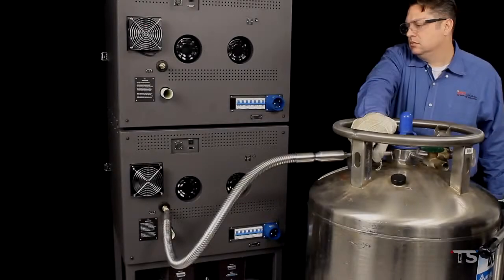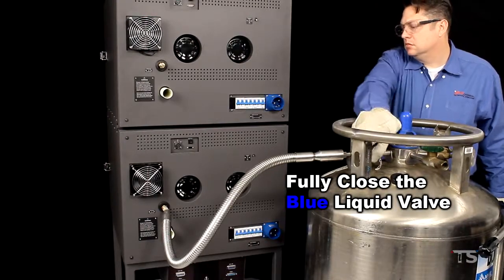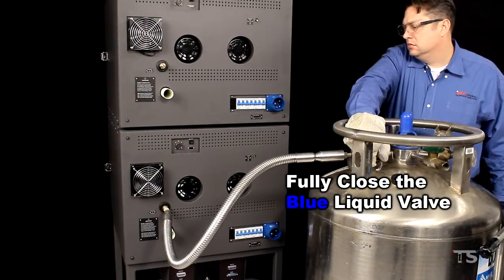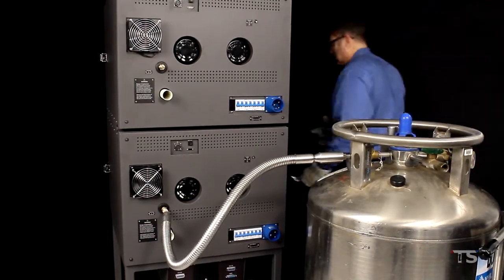When you are ready to disconnect your LN2 lines, you will need to start by fully closing the blue liquid valve at the Dewar. This will shut off the flow of LN2 to your chamber.